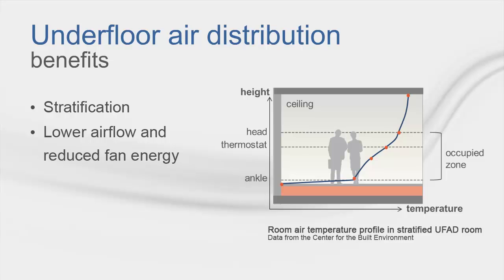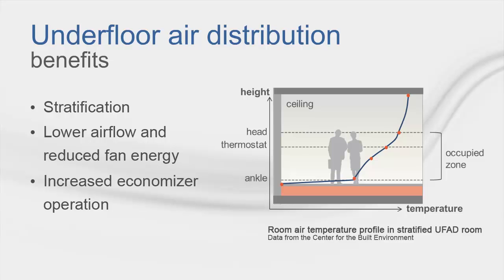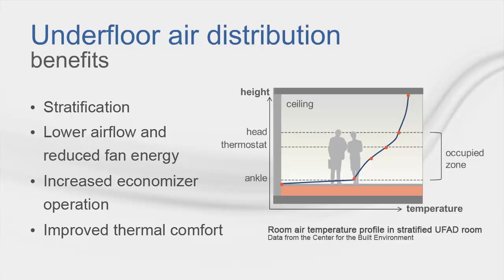As a result of the higher supply air temperature, the potential exists to increase airside economizer operation hours in certain climates. Lastly, thermal comfort is key for a UFAD system. Since air is being delivered through the floor, the potential exists to place diffusers near the feet of the occupants, which can improve thermal comfort. This allows for ventilation air to be directly delivered to the occupants, so the efficiency of delivering ventilation increases, which also improves indoor environmental quality.